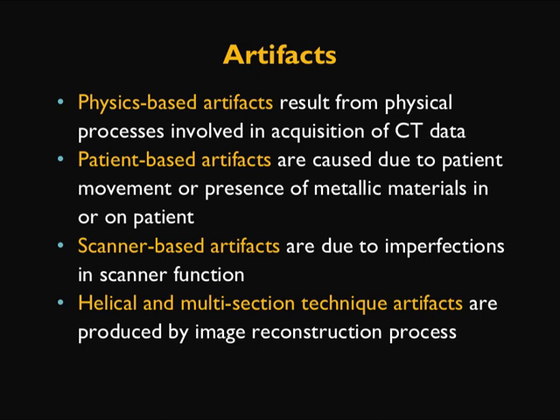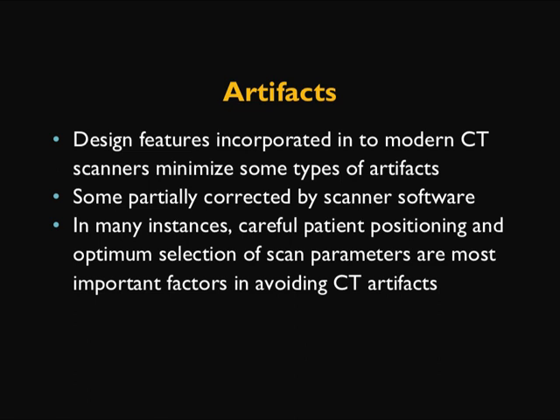The objective of these podcasts on artifacts is to go through each of these categories, provide examples, explain how they are caused, and how they can be eliminated. Regarding artifacts, design features incorporated into modern CT scanners minimize some types. Some artifacts can be partially corrected by software provided by the scanner. In many instances, careful patient positioning and optimum selection of scan parameters are the most important factors in avoiding CT artifacts.